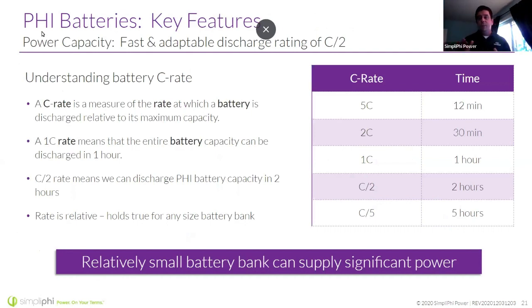One of the terms we'll use in batteries generally is the C rate. Generally speaking, the C rate is the rate at which a battery can charge—so a 1C rate means the battery can be charged in an hour, and conversely discharged in an hour. If you're coming from lead acid, you may be used to C5 or C10 rates, meaning the battery can't be charged in anything fewer than, say for C5, 5 hours. Similarly, getting all the energy out of the battery would take a full 5 hours. With our C/2 rate, we can discharge our batteries at a very high rate—a 3.8 kilowatt-hour battery can be discharged in 2 hours, meaning during that time you're getting 1.9 kilowatts, which is a lot.